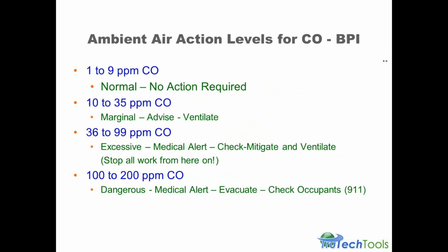Now this is a review of what the BPI standards say, and I hope I'm up to date with them. I'll make sure I double check these. We're talking about 1 to 9 parts per million carbon monoxide as a normal range, or no action required. Then between 10 and 35, advice would be given to ventilate. And between 36 and 99 parts per million, you're getting into an excessive area, and we should really stop and check, ventilate, and get people out of the structure and start to really get concerned. And then 100 to 200 is a medical situation, and everything should be shut down and people moved out of the structure if you measure that much.